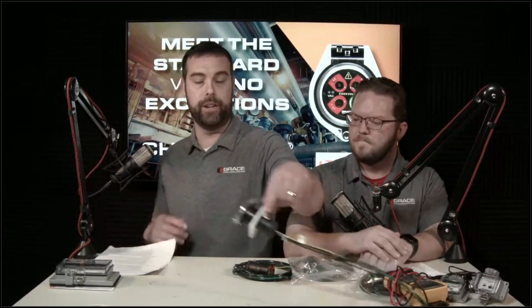Our PESDs are permanently mounted on the outside of your electrical enclosure, tapped in parallel to your source voltage. They provide a safer alternative to using an adequately rated portable test instrument for testing and verifying both presence and absence of voltage. The key question is: is there voltage? These products answer that question — is there voltage, and is this safe to continue working on?